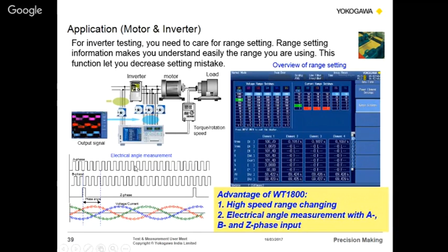The high speed signal capture is 5 milliseconds. With a 5 millisecond response time, it is not difficult for the power analyzer to adapt to the changing signal and capture it. So we can plot the inrush current, which is the motor startup current, and also the power after stabilization. That is the high speed range changing, and electrical angle measurement like A, B, and Z phase in terms of speed. If you see the pulses here, these pulses can be used to calculate the phase angle of the A, B, Z input of the speed.